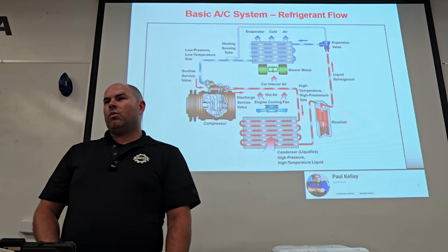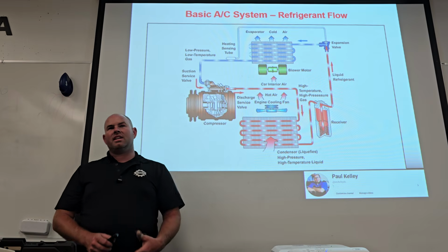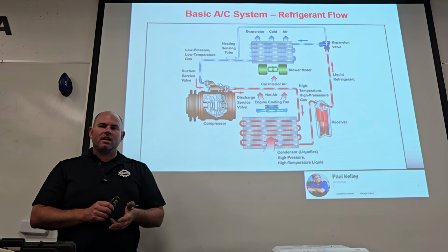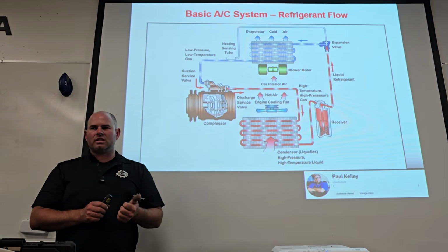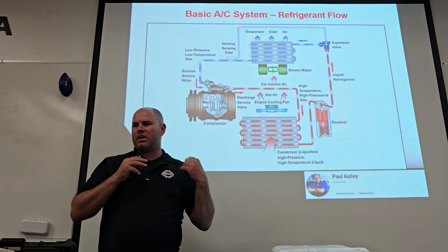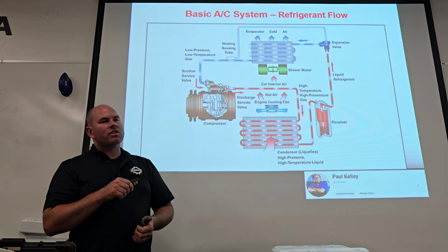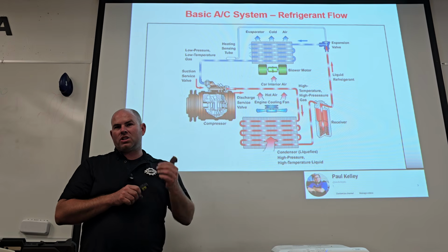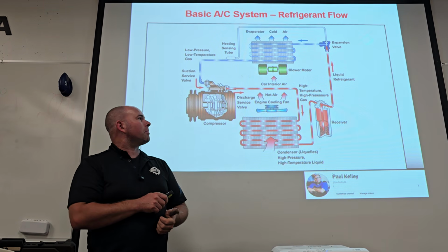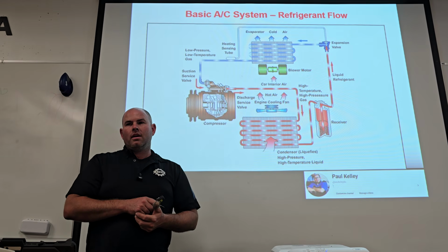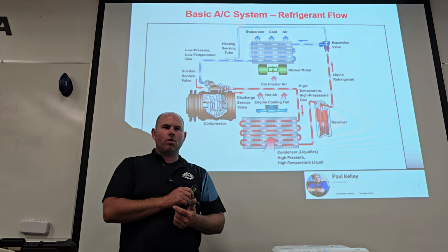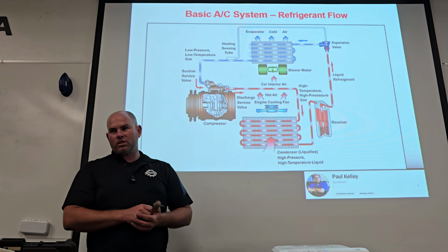Yes, but what's interesting is, it didn't change states or anything, so it still has a similar amount of BTUs. It goes from hot to cold mainly because it goes from high pressure to low pressure, but there's not a major change of energy right here. There's just a big change of pressure, and therefore a big change in temperature. This doesn't perform the cooling. That makes sense? This is here so that we have a high pressure and a low pressure. We need a high pressure and a low pressure to force the condensation and force the evaporation.